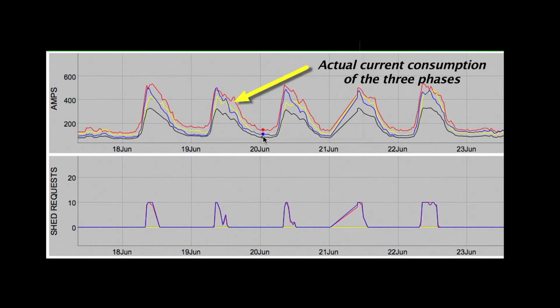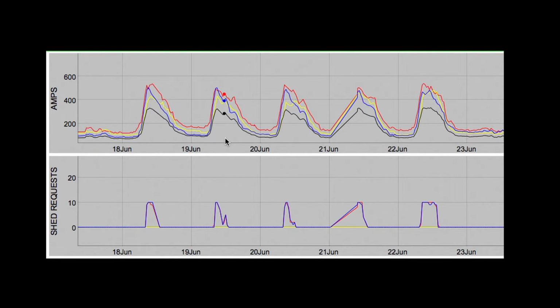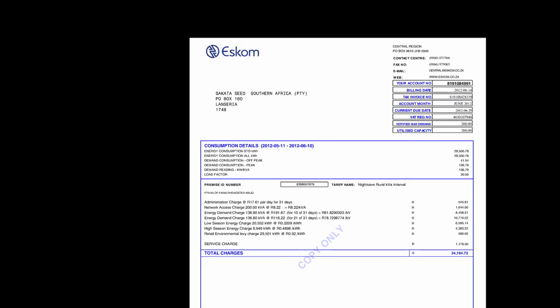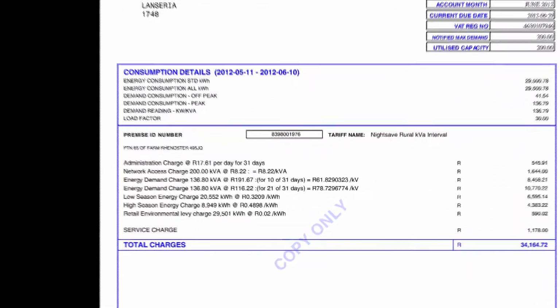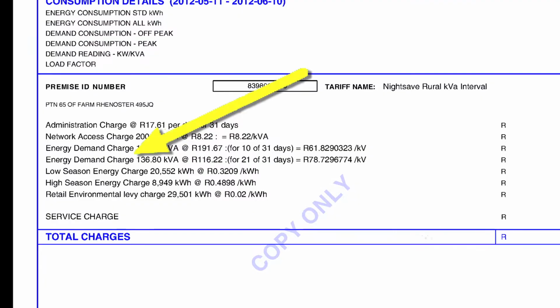The red, blue and yellow lines represent the actual current consumption of the 3 phases at any given time. Since we are mainly concerned with managing the demand on the electrical system, that is represented by the black line and is expressed as kVA or kilovolt amps, averaged over half an hour. That is calculated exactly in accordance with the national demand billing criteria. The maximum demand is what you pay for, as reflected on your electricity bill.